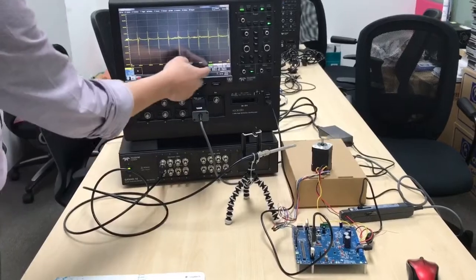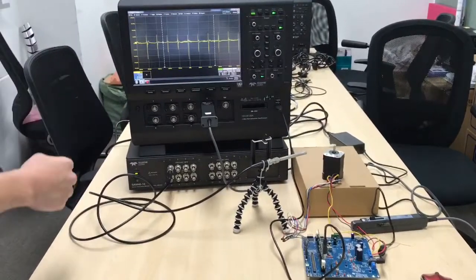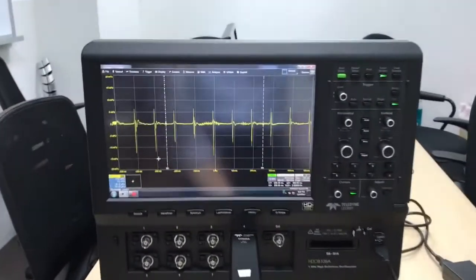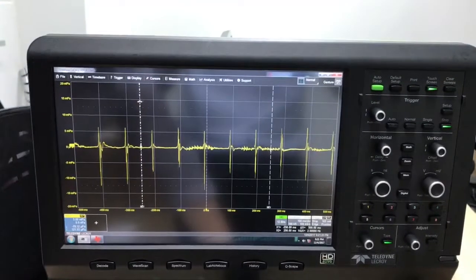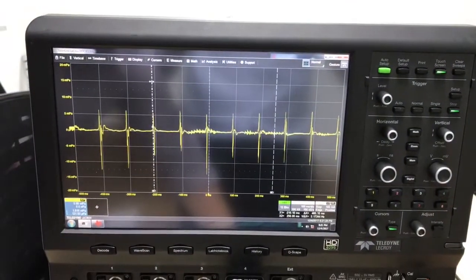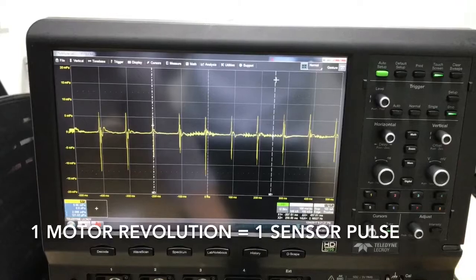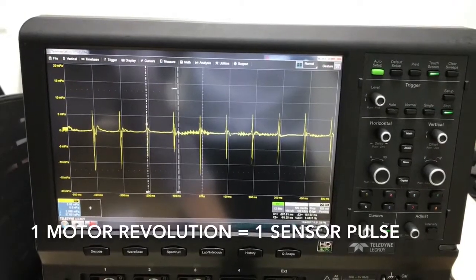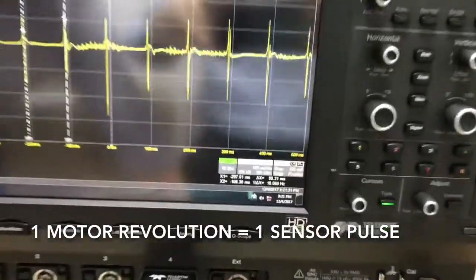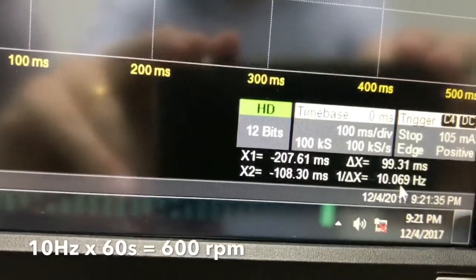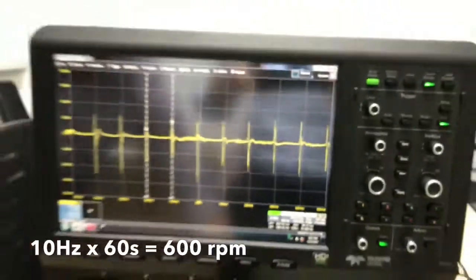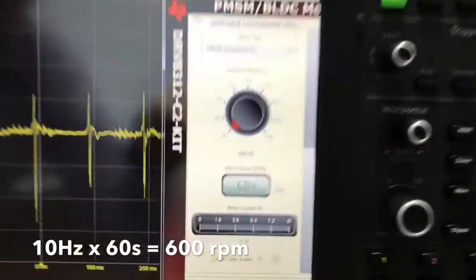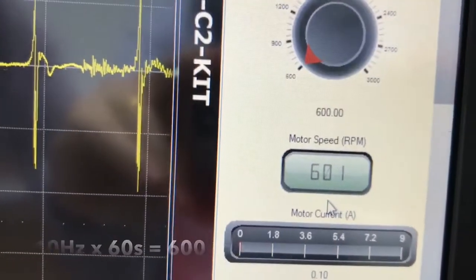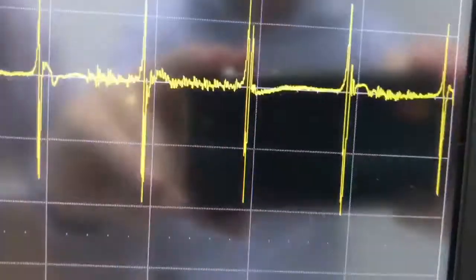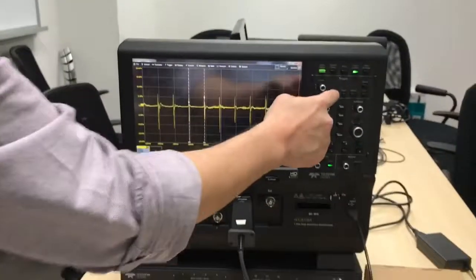For example, I can use a cursor and look at the period of the pulses from the sensor. So the period here is 10 Hertz. 10 Hertz times 60 would be 600 RPM, which is actually the motor speed right now. So you can see that everything is correlated in real time.